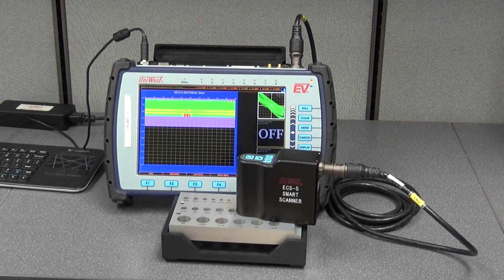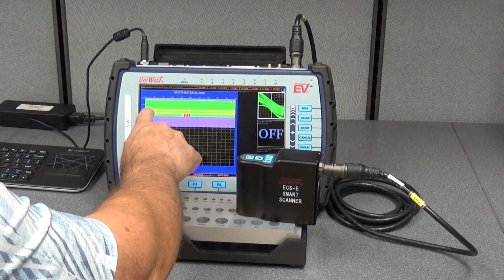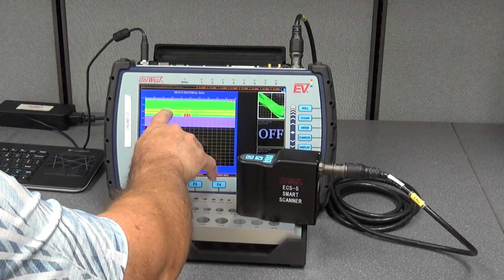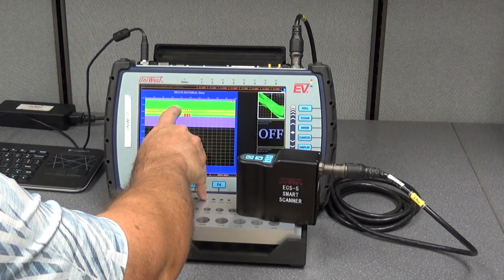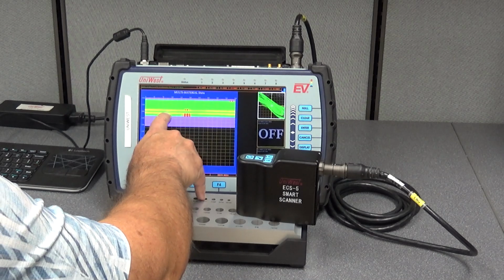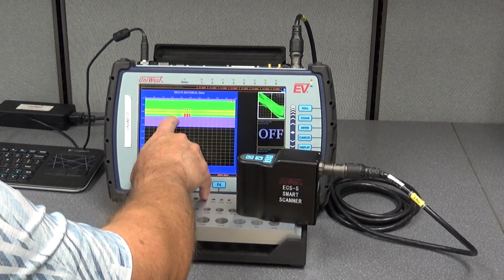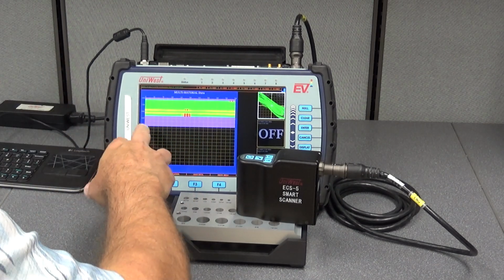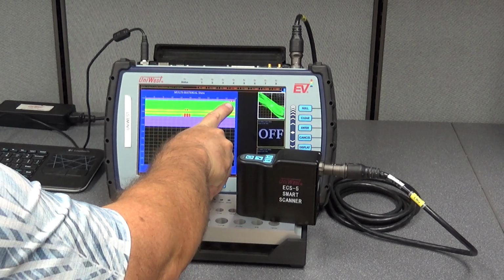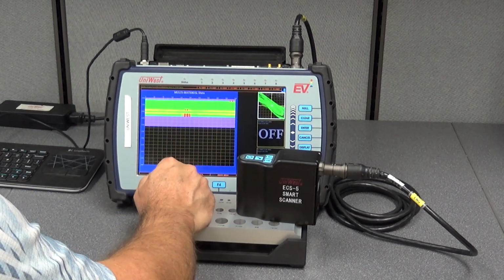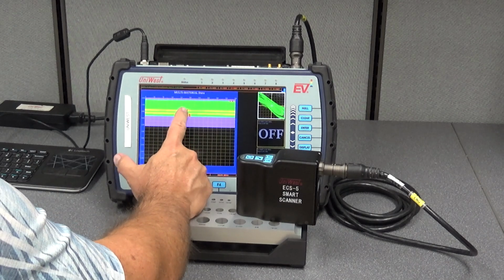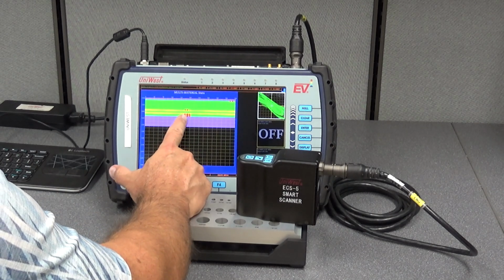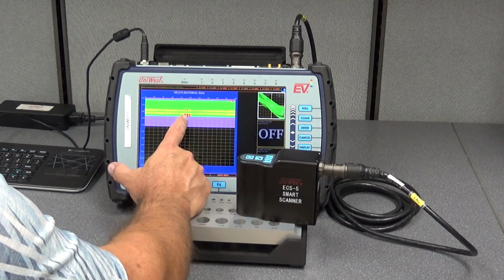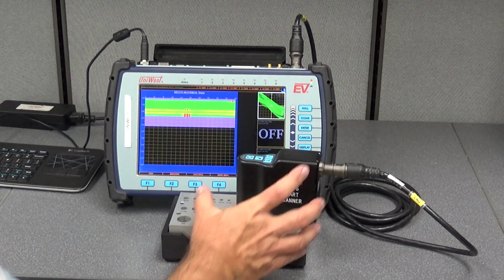Okay, so it's done scanning the hole. This reference standard has 3 layers of aluminum, so there's 2 interface lines down here, and you can see those 2 interface lines indicated by the yellow. So the first interface is between layer 1 and layer 2, and then the second interface line is between layer 2 and layer 3. Then also what we're seeing, the red is the EDM notch at the very top, EDM notch at the bottom of the first layer, and then there's a through notch in the 3rd layer, and we see that on the screen.